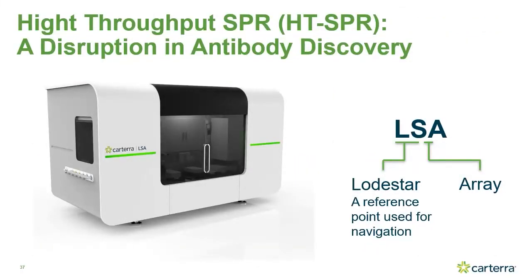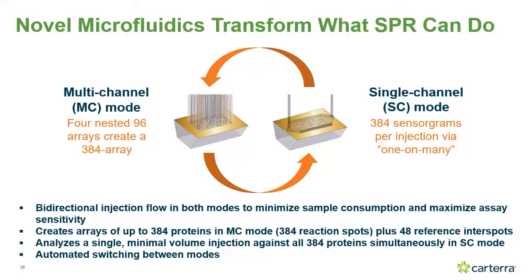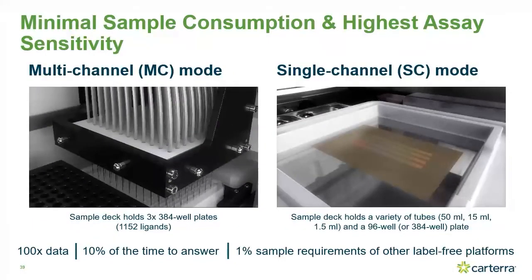Now switching gears to talk about the LSA platform. LSA stands for Lodestar Array, and it is a high-throughput SPR array system. What makes the LSA ideally suited for high-throughput SPR is its two relatively independent fluidic systems that address the same sensor chip surface: a multi-channel mode enabling continuous flow microspotting — also referred to as the print head — capable of up to four nested 96-array prints to create a 384-spot array, and a single channel flow mode that injects one sample over the entire array surface.